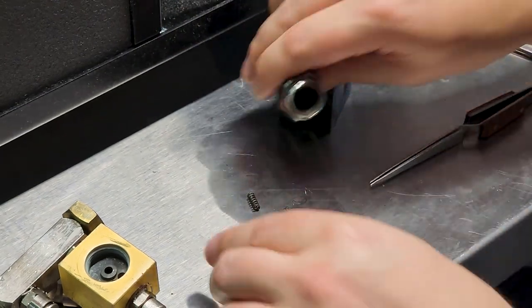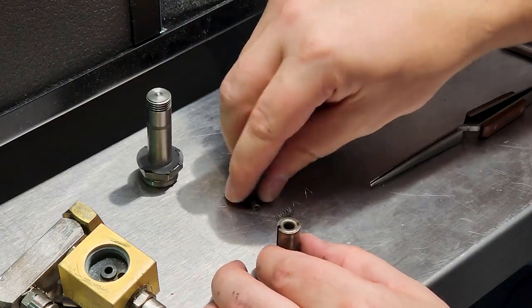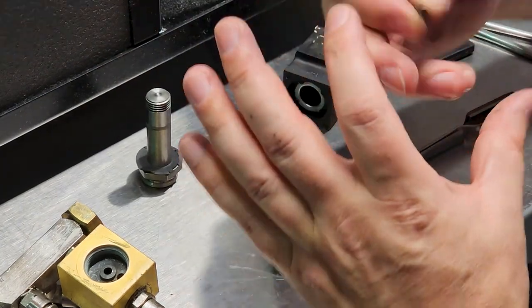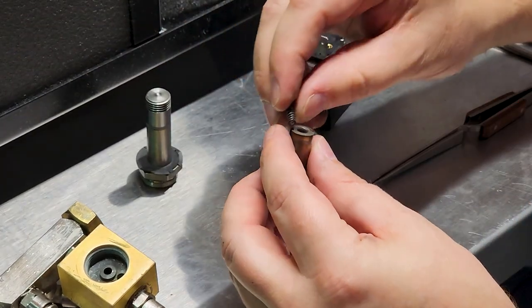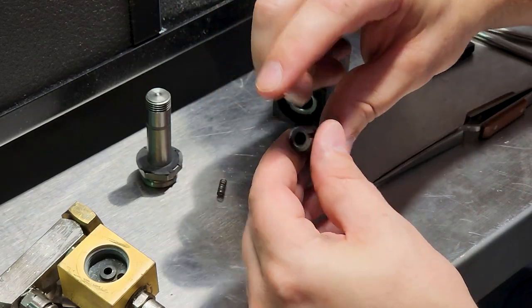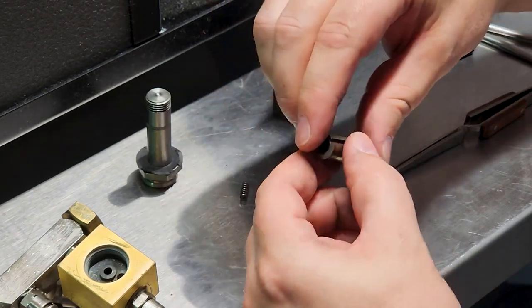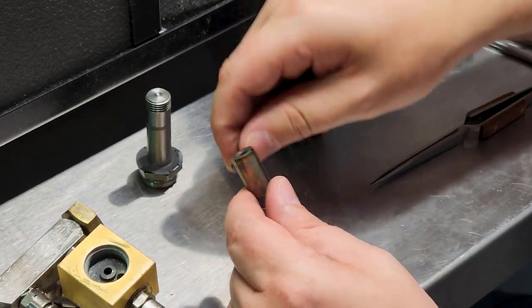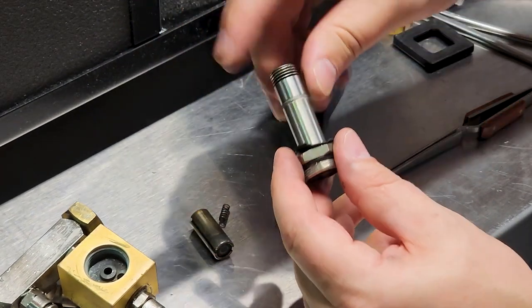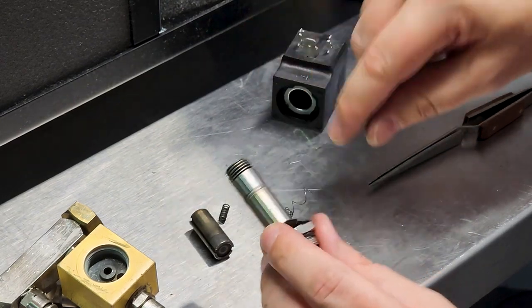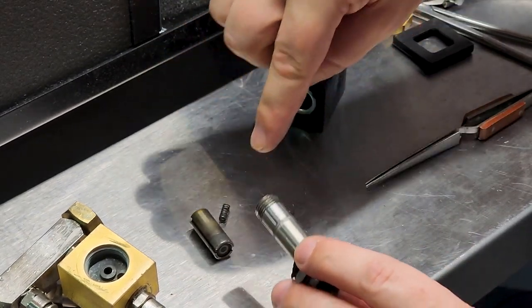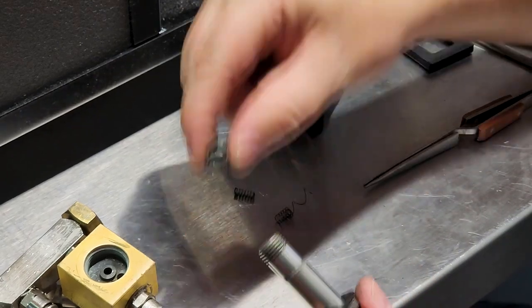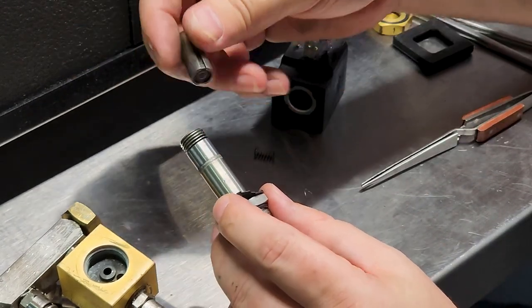This is your valve body, and what I think is happening is this is supposed to be a spring-over-spring type of suspension in here. And because the springs were all jammed up, this guy here was hitting extra hard because these are also dampeners. And that dampener is supposed to alleviate some of that vibration. But because it was so rigid and almost maxed out on the spring, it was allowing the piston to vibrate, which was that sound that you heard.